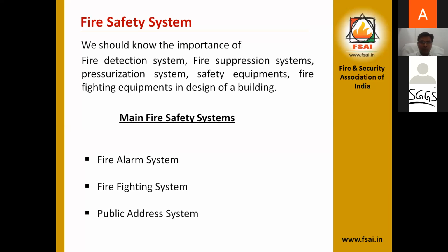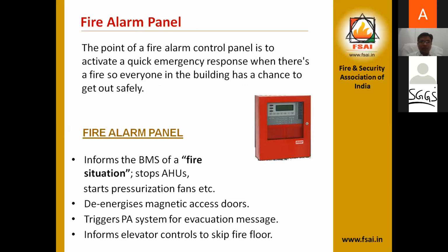The first one is the fire alarm panel. The fire alarm panel is a panel which controls and activates a quick emergency response when there is a fire, so everyone in the building has a chance to get out safely. It is located outside the building so that any incident in the building is immediately informed to the fire alarm and it will try the rescue operation. It informs the BMS, the building management system, of a fire situation to stop the air handling units, start pressurization fans, etc. It de-energizes the magnetic access doors, triggers the PA system for evacuation messages, and informs elevator controls so that when any floor is on fire, that floor is skipped by the elevator.